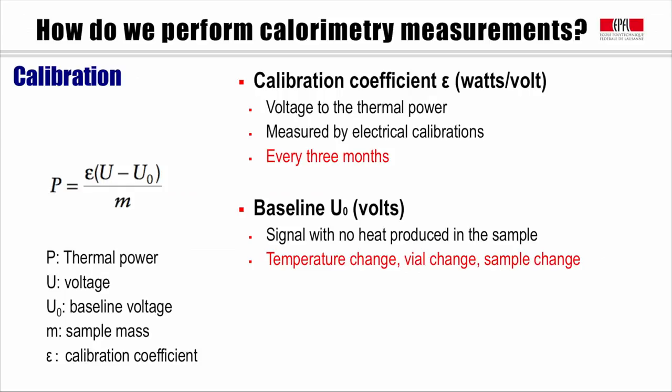Based on heat flow measurement principle, the thermal power P is proportional to the voltage signal from the sensor U, as indicated in the equation. To establish the relationship, two parameters need to be determined. They are calibration coefficient epsilon and baseline voltage U0.